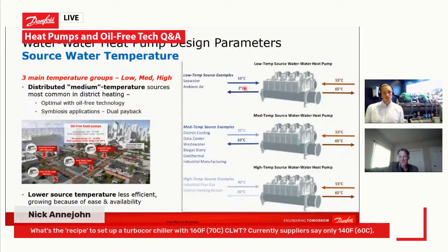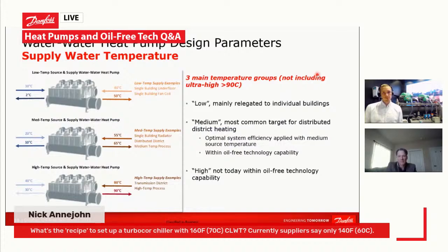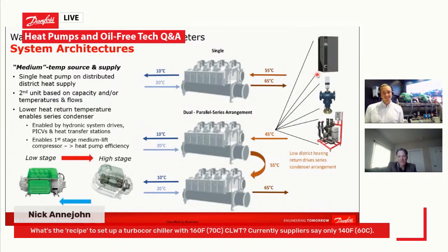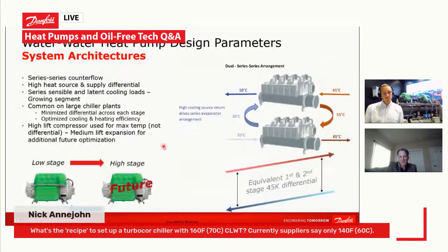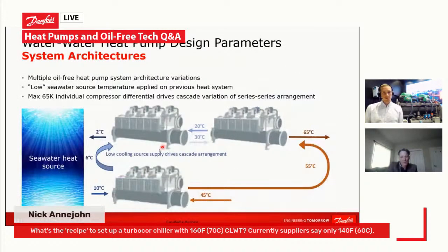So it's more similar to this example. You're probably coming out around 2, and so 55 to 65 with 10 and 2. And I'm jumping ahead again, but the system architecture we would use for that is probably something like this with a parallel series arrangement. You'll use that parallel because of that lower source water temperature, and then series, and then potentially cascade series, which is another evolution of that architecture, depending on the supply water temperature that you're providing.